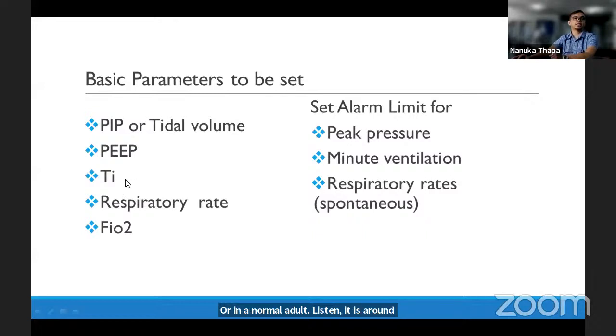Then the inspiratory time. After setting the inspiratory time, the IE ratio will come by itself. The machine will calculate the IE ratio by itself, and the expiratory time will be the remainder after subtracting the inspiratory time.